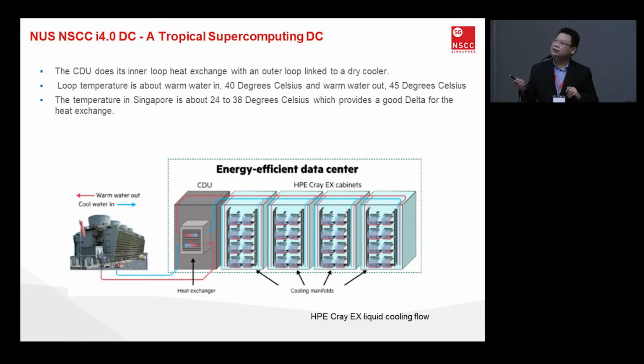Then it goes into the CDU, your cooling distribution unit, where it does the heat exchange with a second internal loop, which goes to the dry cooler. Now this dry cooler internal loop, the temperature is much lower. You're looking at roughly 35 going in.